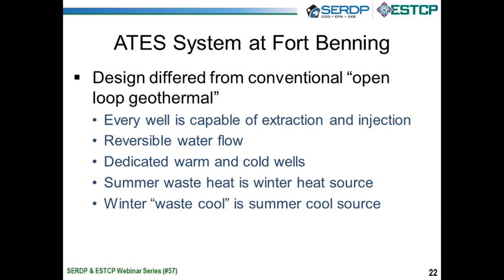Conversely, in the wintertime, we're running the water through the building, the warm water. The building extracts its own waste heat that we stored the previous summer to heat the building, and then it creates waste cool, or chills the water. And in the deep south here, obviously, we need some help, so we're running the adiabatic dry cooler to get it even colder. We put that cold water down into the cold wells, and that is our summer cooling source later in the year.